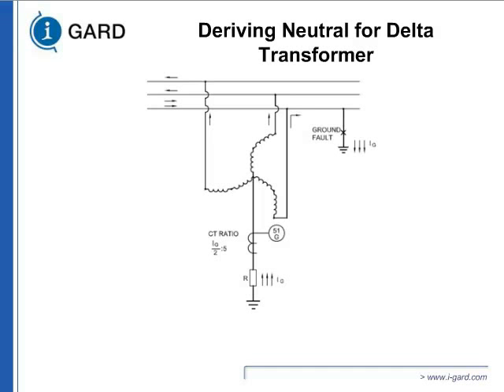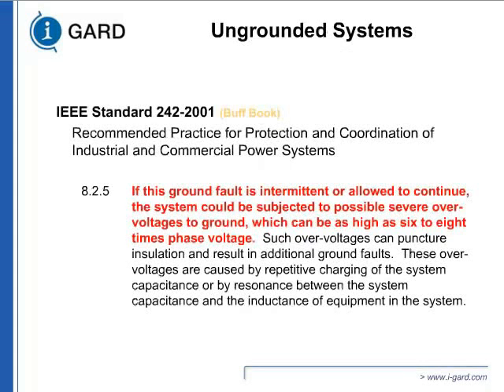There's another quote from the Buff Book, which I hope you can see in the scene. The hardest part is if the ground fault is intermittent. Then the voltage keeps on rising, and that's where the damage occurs. Buff Book says it can go as high as 6 to 8 times the phase voltage. I'll show you a schematic in a sketch. Technically, they can go to infinite value, but at 6 to 8 times some damage will occur and the system will shut down.